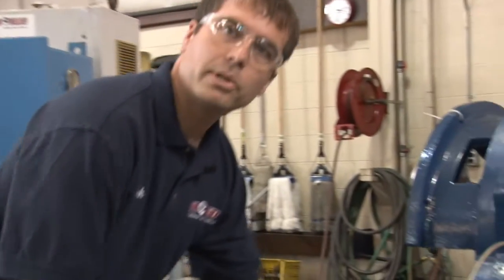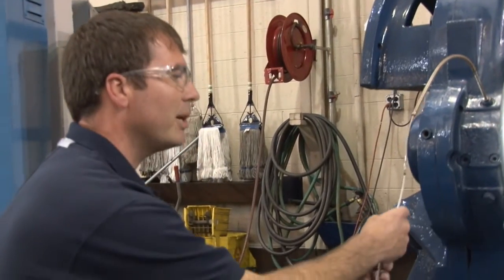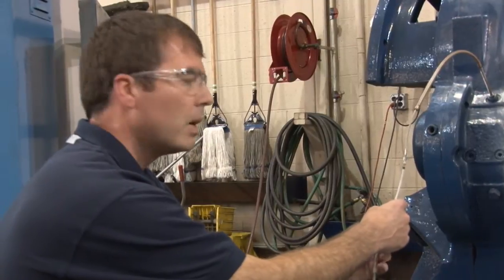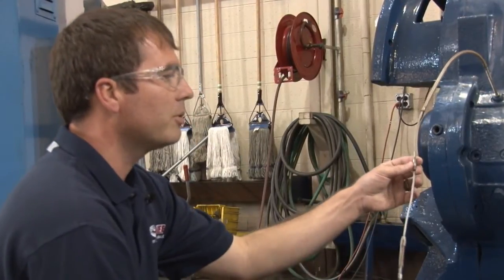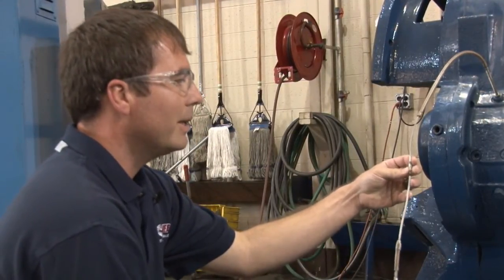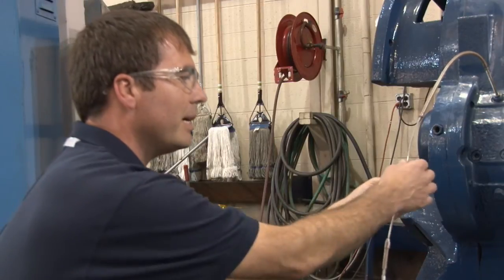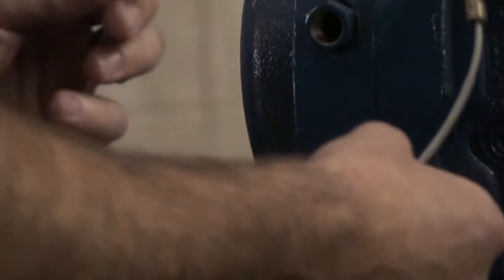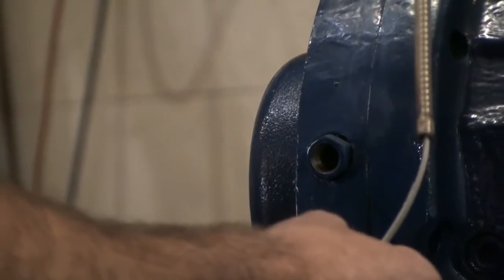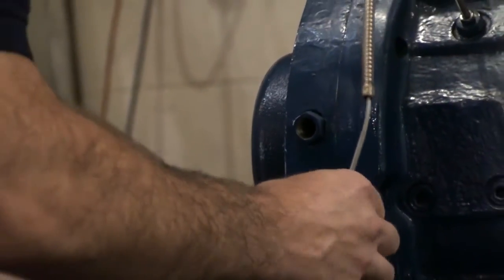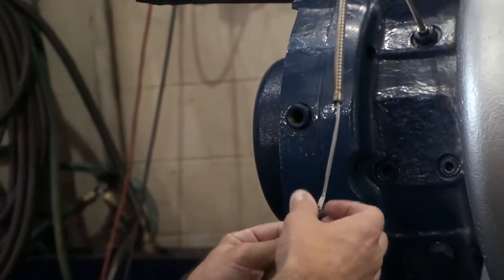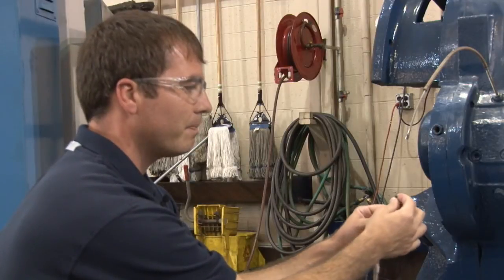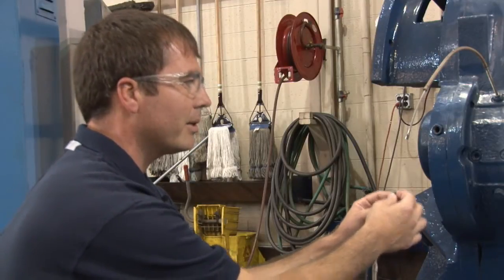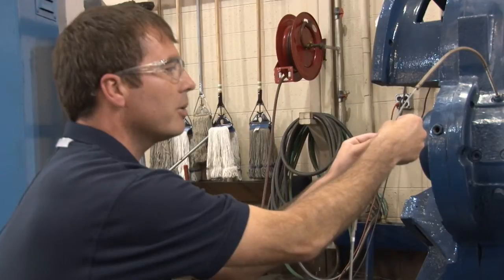The first thing I would do if I experience a vibration alarm or trip, I would come over to the machine and I want to check the connections are tight and clean. I would disassemble the connection here, look inside, spray these with contact cleaner. You can do this here at the end, this end of the cable, the probe itself. Make sure they're clean.